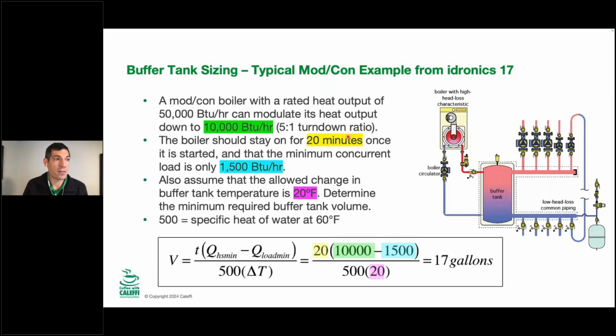20 minutes is a good place to start. If you put in 5 minutes here, you're not really providing much of a buffer. We want to give that boiler a little bit more time to rest. You could do 1,000 minutes here and have a 500-gallon buffer tank. That would be overkill in a lot of cases, but mostly we just don't want, especially a boiler or a heat pump, to cycle 10 times in an hour. 20 minutes is probably a good place to start.